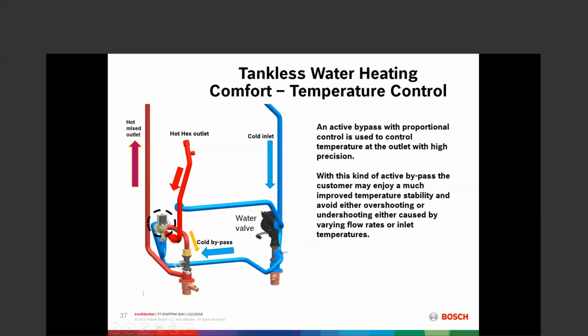The response of OptiFlow then is to open this bypass valve, which then acts as an injector. It is not a true mixing valve. It's actually injecting cold water into that hot water stream to then manage that allowed overshoot back to set point. And we're confirming all of that with another NTC thermistor here watching the temperature as the water is actually leaving the cabinet. So that's what active bypass does for us. It maintains the temperature or ensures temperature stability.